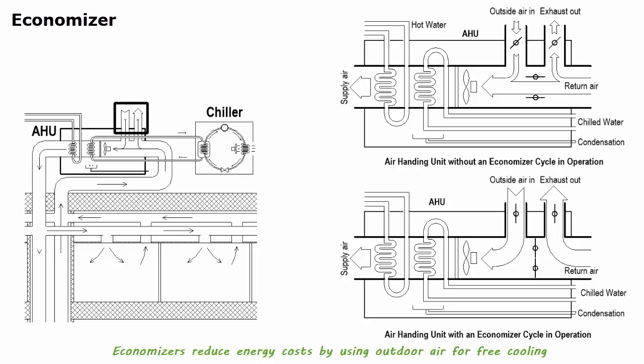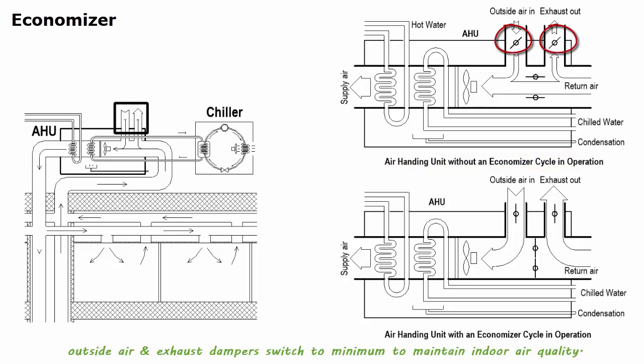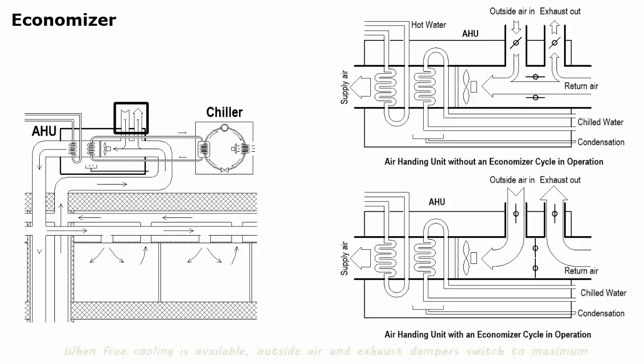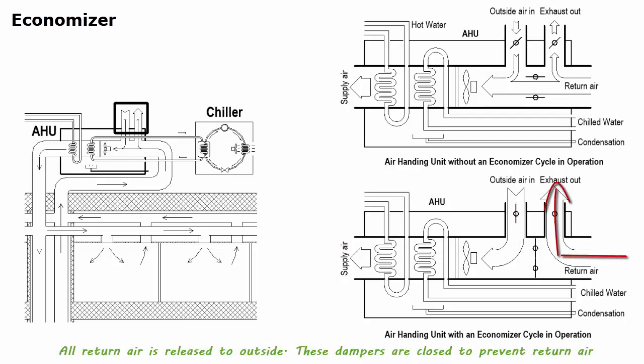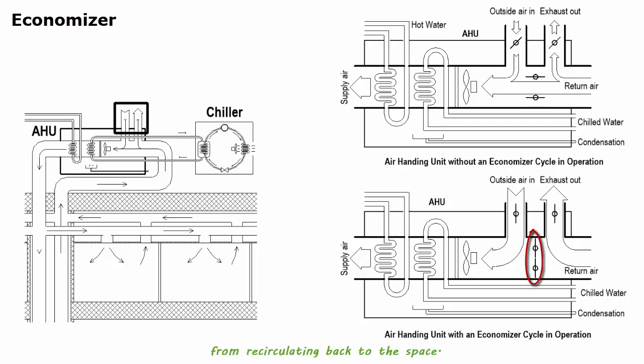Economizers reduce energy costs by using outdoor air for free cooling, and it causes the compressor to run less. When free cooling is not available, outside air and exhaust dampers switch to minimum to maintain indoor air quality. When free cooling is available, outside air and exhaust dampers switch to maximum to use only outside air to cool the space. All return air is released to outside in that case. These dampers are closed to prevent return air from recirculating back to the space.